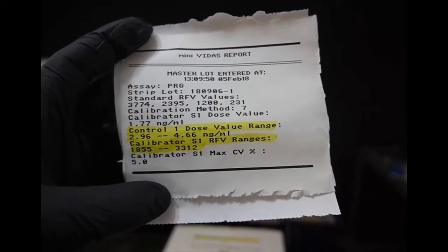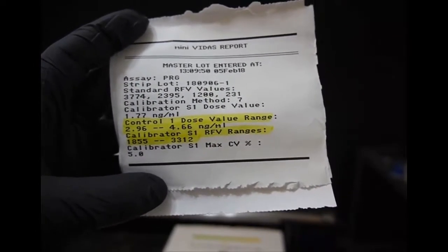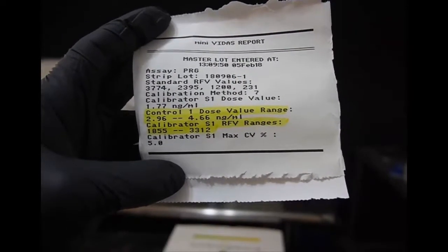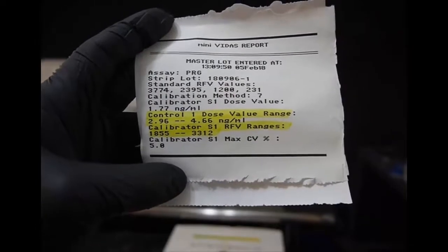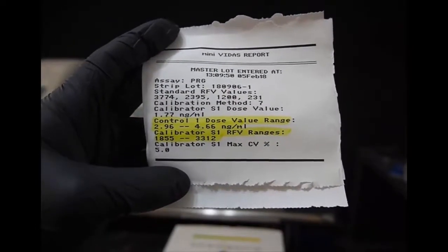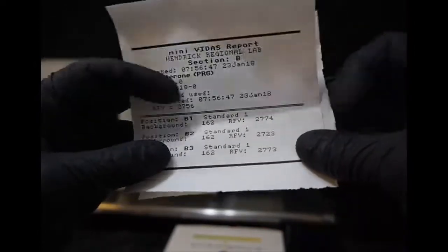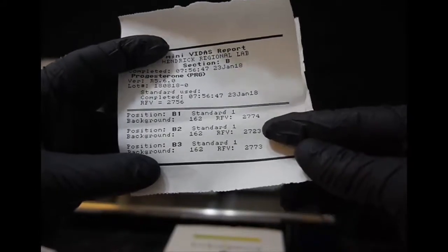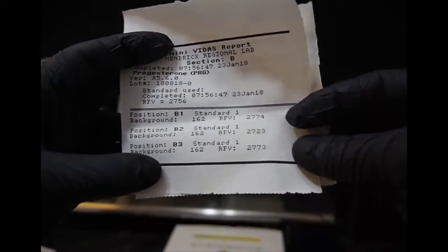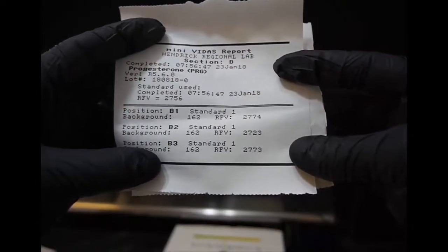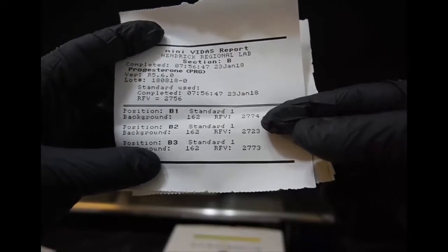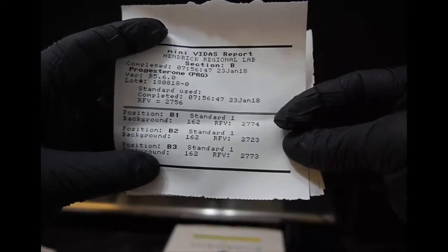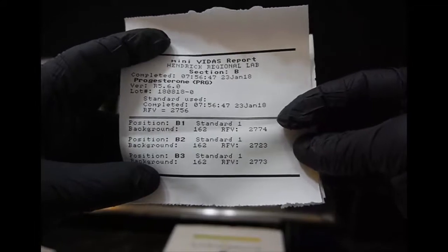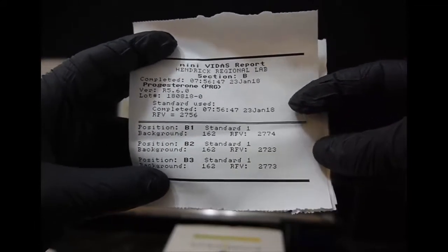Below that are the RFV values. Those are used in the manufacturer and calibration curve. Next is the calibrator S1 RFV, which stands for relative fluorescent value range. When your calibration is finished and prints out the value, you want to be within this range. As you can see in a previous calibration, these will be the numbers you are looking at. The machine will automatically reject the calibration if the CV is greater than 5% or if it is outside of range, and then you will at that point recalibrate and re-examine the kit materials and the reconstitution.